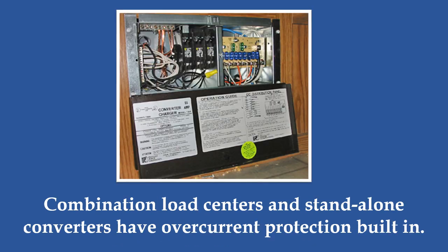Other sources of 12-volt power in RVs are the standalone converters and the combination load centers. Both are designed with built-in overcurrent protection that protects all circuits downstream of those devices. The 12-volt panel board then further reduces the protection size to the individual circuits, with most breakers being 15 and 20 amps that are connected to 14 and 12 gauge conductors respectively. The RV low voltage electrical systems are also designed so that both the converter and the battery power feed 12-volt power to the branch circuits through the same 12-volt distribution panel board.